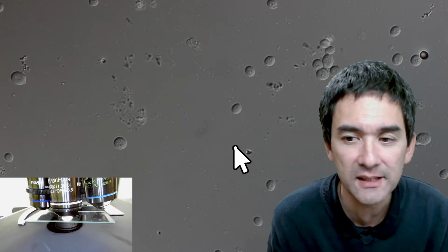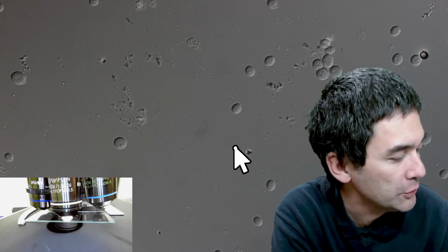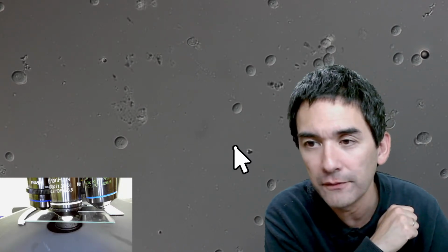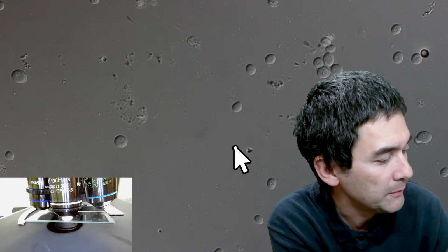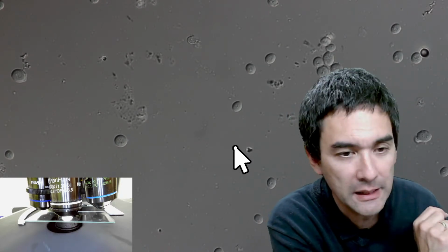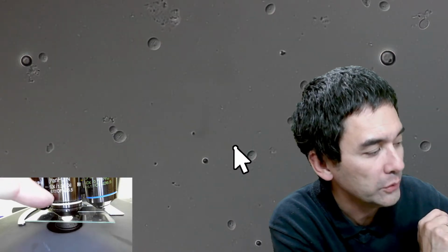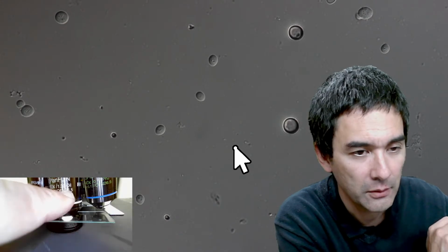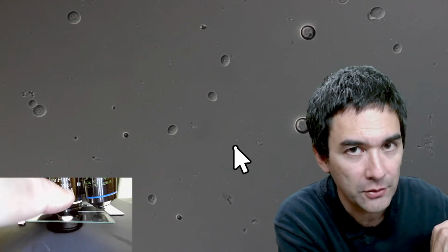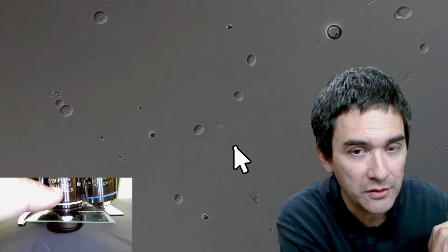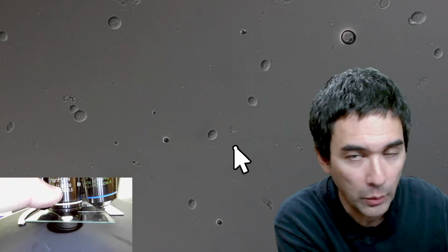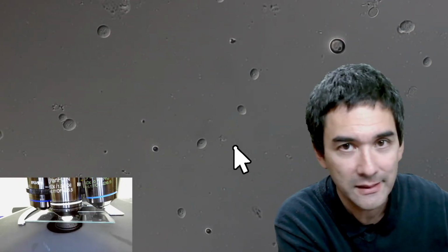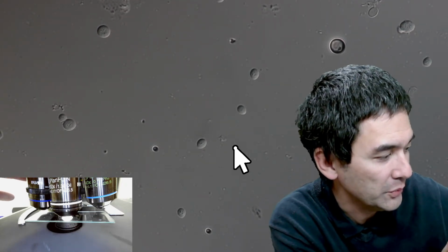In order to summarize this, especially for those of you who join in maybe a little bit later, and there's also a comment I want to make concerning the magnification later on: be careful that you do not contaminate anything with oil. Use immersion oil only on the oil objective, the one that has the word oil printed on it. I've received questions from some beginners some time ago who wanted to improve the quality of the image, and they tried to use immersion oil on all of them. That's dangerous. Don't do that.